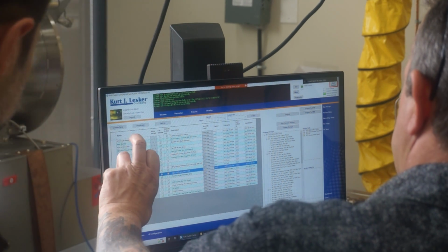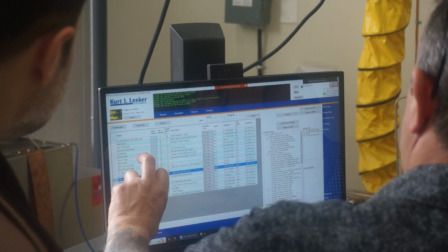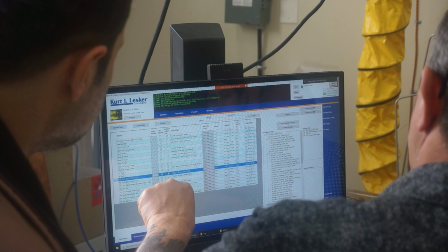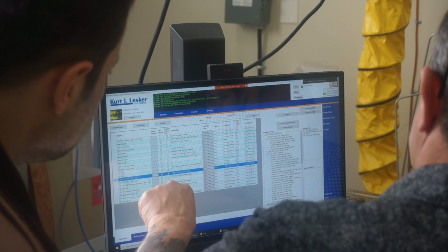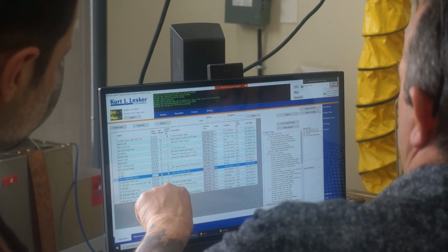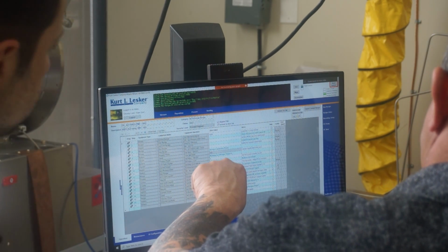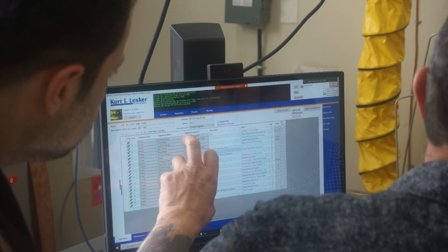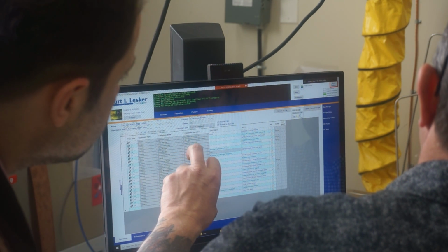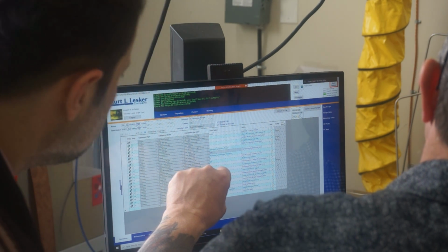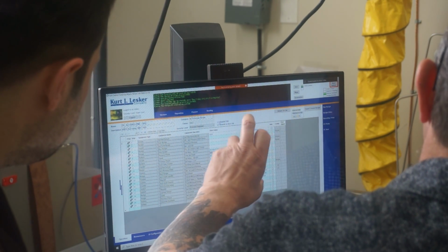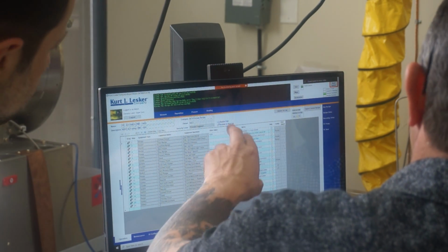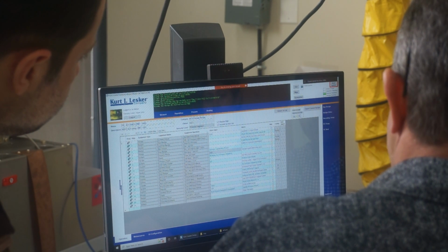So on the columns you have the name, view recipe, you can click on it. You can hit edit disable or include and run it. Edit disable gives it a safety step: if I go into this recipe, I would have to uncheck this before I could do any editing. So somebody deliberately has to take action to edit the recipe. You don't have to have this checked, but it's not a bad thing to have it checked if you don't want somebody to accidentally change it.